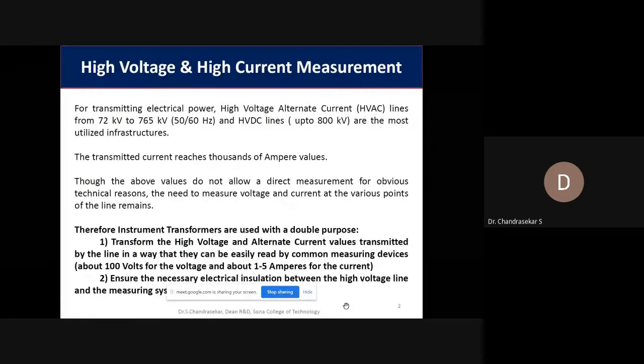Even in Europe and other countries, people are also using 110 kilovolt or 220 kilovolt underground cables. Like that, the power transmission and distribution system consists of mainly 2 components. One is the transformer, and another one is the cable. In such a case, I don't know whether you people know or not, a high voltage transformer, you cannot imagine, will occupy almost one master bedroom size of space.